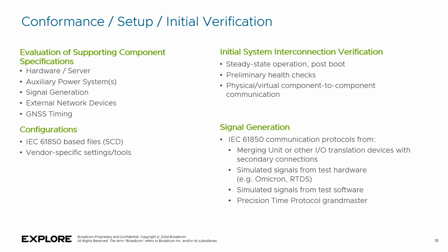In terms of protocols, IT and OT don't necessarily use the same, but there are some common ones like SNMP and syslog that we can use instead of doing conversion. And then, of course, get this set up and get everything talking to each other. Signal generation in the lab is not from high voltage equipment, of course, but we can simulate the signals either by injecting secondary or by just straight out simulating those 61850 signals.